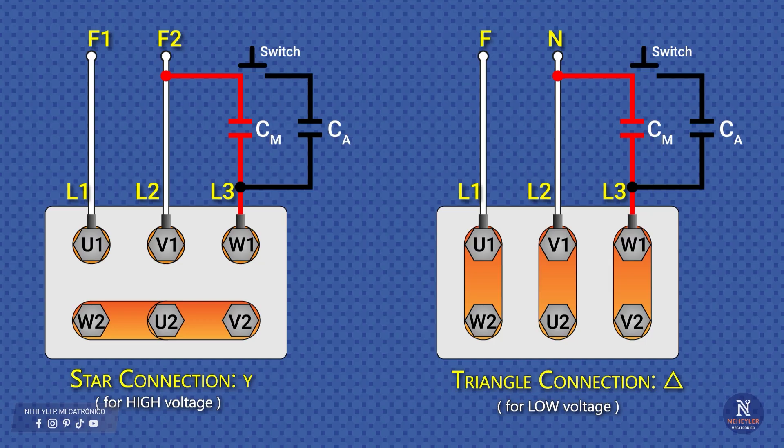However, in many cases the starting torque provided only by the run capacitor is not enough. That is why a start capacitor is also used. It is connected in parallel with the run capacitor, but through a switch, a push button, or a timer, which will be explained later. In this way, the start capacitor only works for a few seconds at the moment of starting, and then it is disconnected automatically or manually.